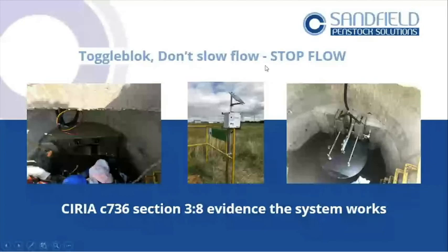Coming to the end now. Toggleblok — don't slow flow, stop flow. The idea of Toggleblok is to stop flow in the event of an emergency. It's not a flow control device — it stops flow. Here's a couple of installations, including one recently done for Toyota. You've got the control panel running on solar power so it's always online — not waiting for mains power. A simple plate is loaded into a headwall, the valve sits on the outlet side, and in the event of an incident it drops and stops the flow.